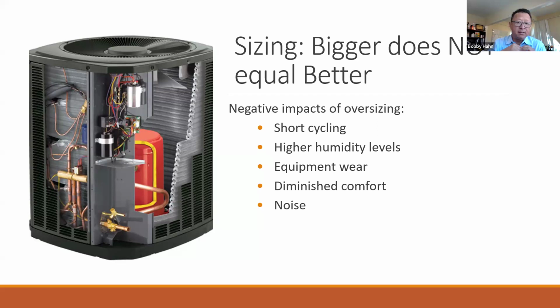Higher humidity levels, because you're going to wring out the air so fast, and then it's going to come back and go high up and down. Equipment wear, you're going to be wearing out the compressor. So you're definitely going to go back to the humidity level. You're going to have diminished comfort. You're going to overcool or overheat, and then your noise is also going to be considerably higher if you're cycling on and off.